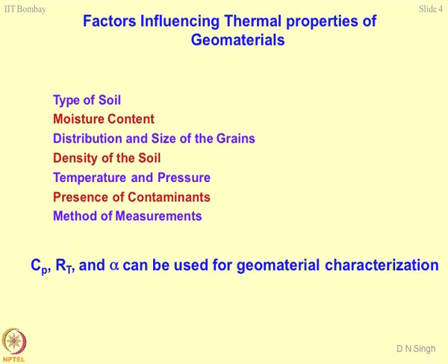So, this is where the type of the soil, moisture content, and distribution of the size of the grains of the soil become very important parameters in finding out whether a project is feasible or not, because there is a limit to modify the soil based on its thermal properties. And when you say modification of the properties, it's understood that you are trying to lower the resistivities. Clear? So, in a region like Bombay or most of the coastal regions where you have clays, the thermal resistivities are very, very high. So, you have to modify the entire route of the pipeline or buried cable, kilometers long, by inserting a good material which is known as a good backfill material or fluidized thermal backfill material, FTB. If you work in this area, you will come across the word FTB, fluidized thermal backfill. Fluidized thermal backfills are designed to reduce resistivities of the soil mass.